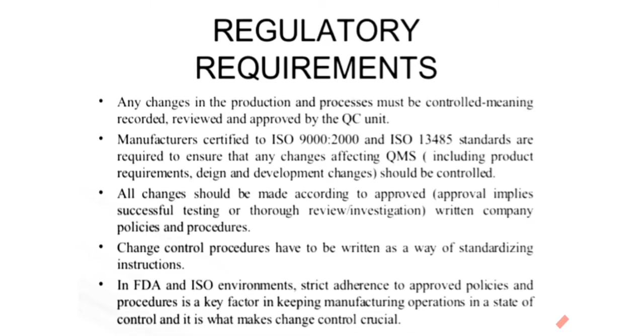Regulatory requirement. Any change in the production and process must be controlled, meaning recorded, reviewed and approved by the respective units. Manufacturers certified to ISO 9000:2000 and ISO 13485 standards are required to ensure that any change affecting the QMS, design and development is controlled. All changes should be made according to approved written company policy and procedure. Change control procedures have to be written as a way of standardizing instructions in the FDA and ISO environment. Strict adherence to approved policy and procedure is a key factor in keeping manufacturing operations in a state of control, and it is what makes change control crucial.